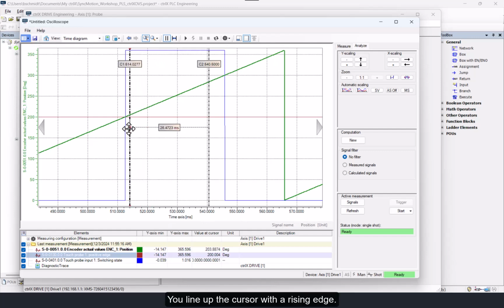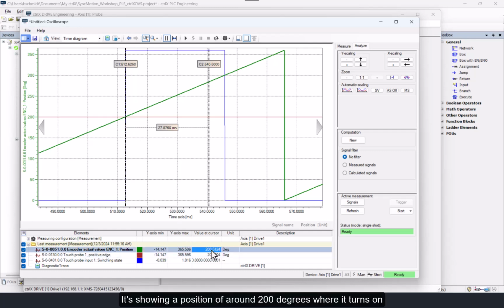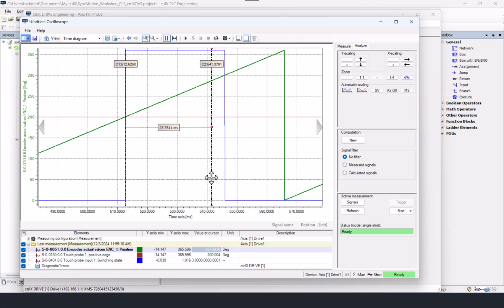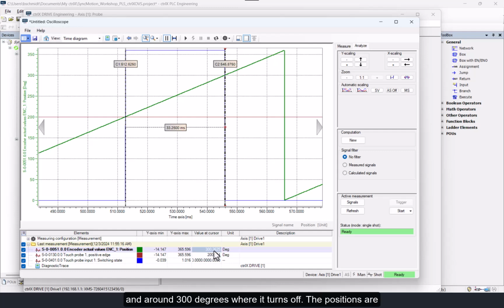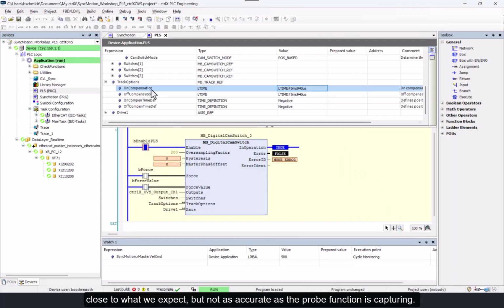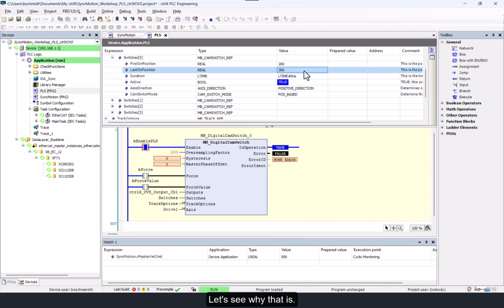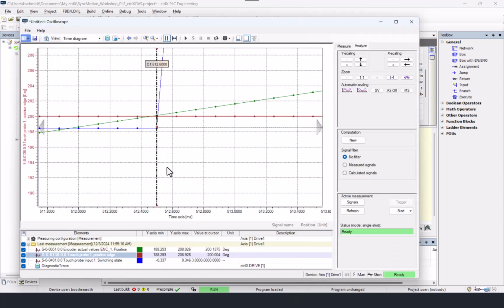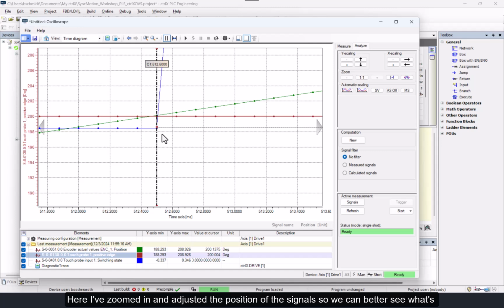If we line up the cursor with the rising edge, it's showing a position of around 200 degrees where it turns on, and around 300 degrees where it turns off. The positions are close to what we expect, but not as accurate as the probe function is capturing. Let's see why that is. Here I've zoomed in and adjusted the position of the signals so we can better see what's going on.